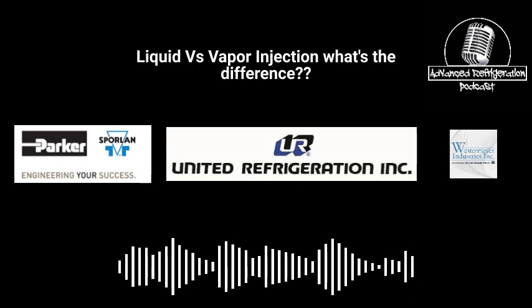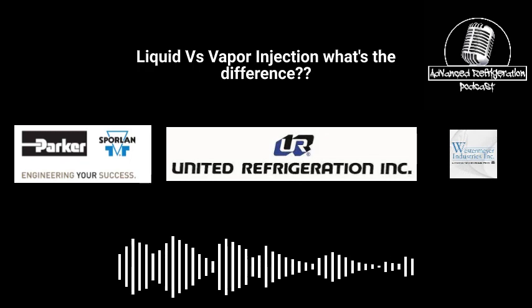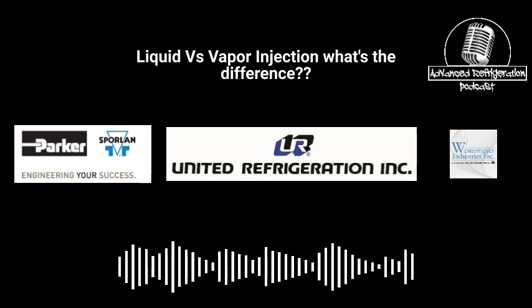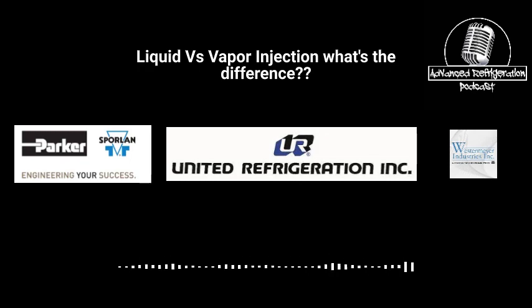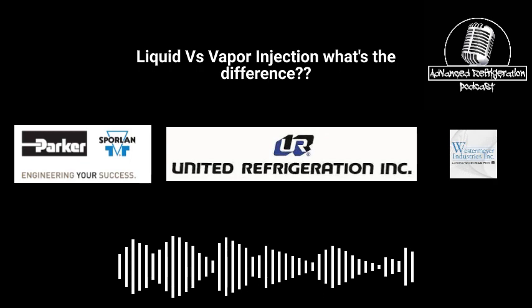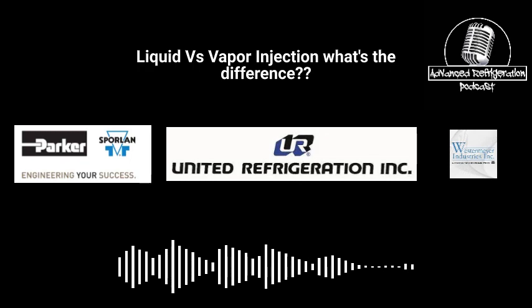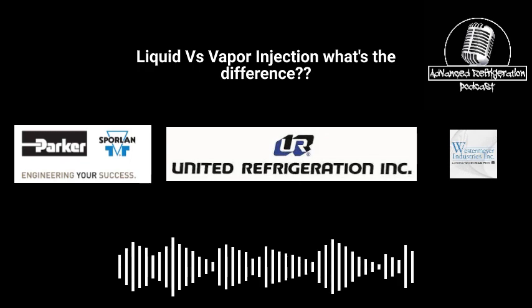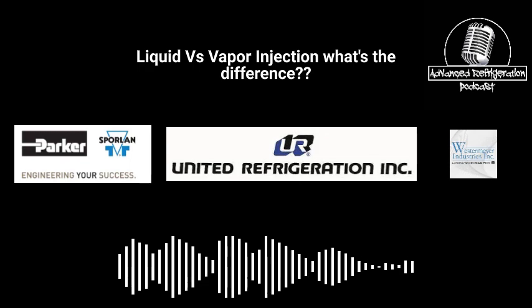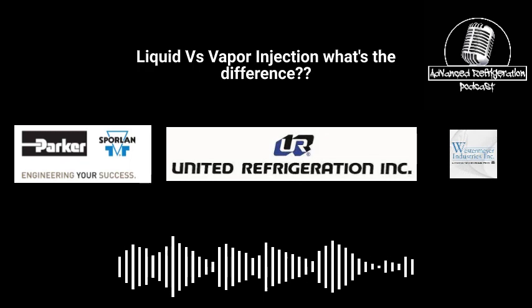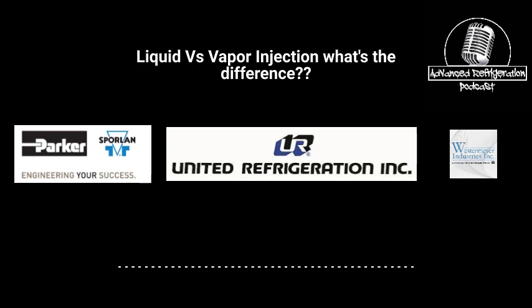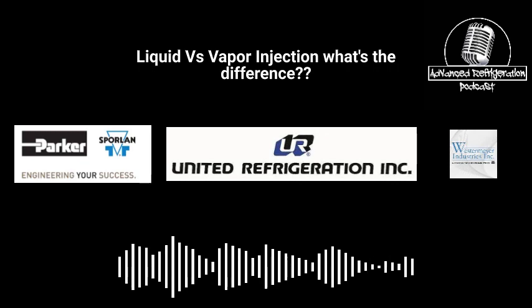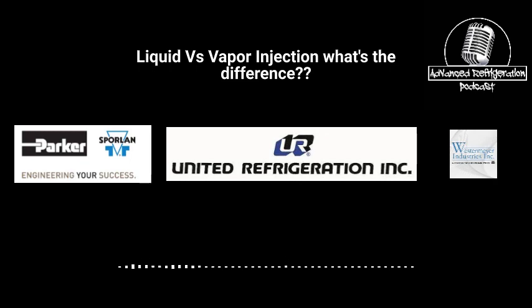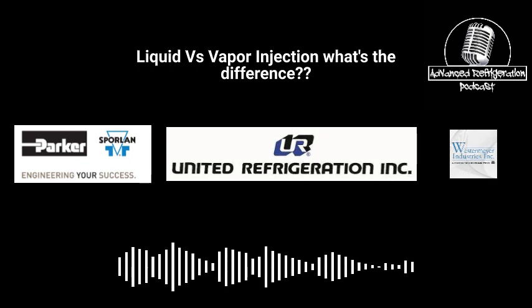Yeah. Just to put it in perspective, guys, on a compound Carlyle compressor, those valves that are feeding liquid into there are typically 1 ton. So it wouldn't take much, putting in one little upsized orifice, where you're overfeeding the thing and not allowing that liquid to boil off. It definitely increases the longevity of the compressors. When I first started working for a company a long time ago, they had a whole bunch of compressors with paint boiling off of them. They were changing out 2 or 3 compressors a year per store. And that went down significantly after we got all the subcoolers up and running.